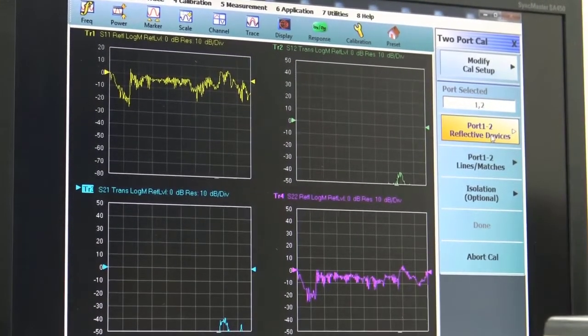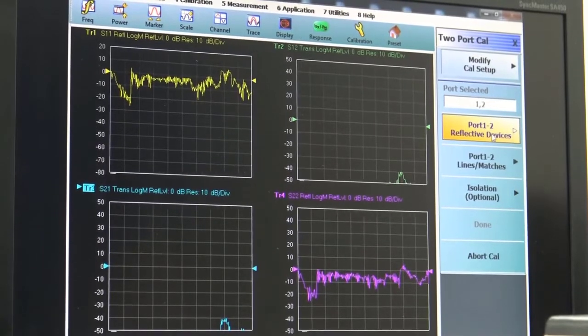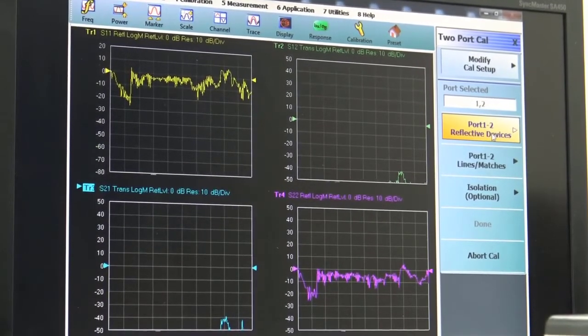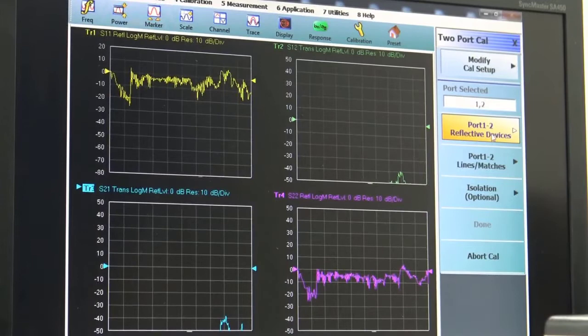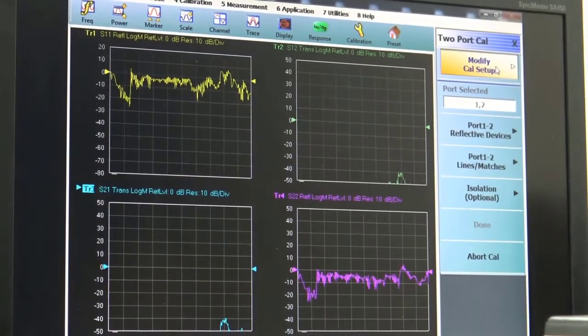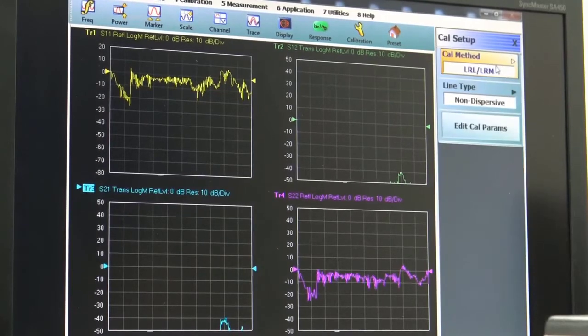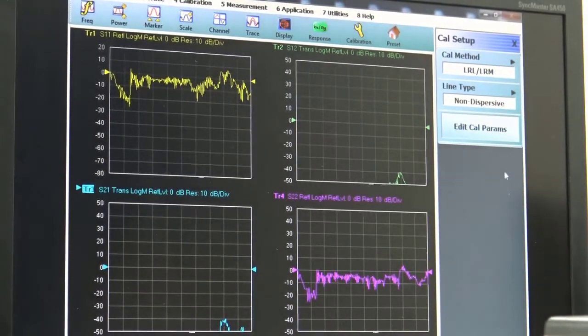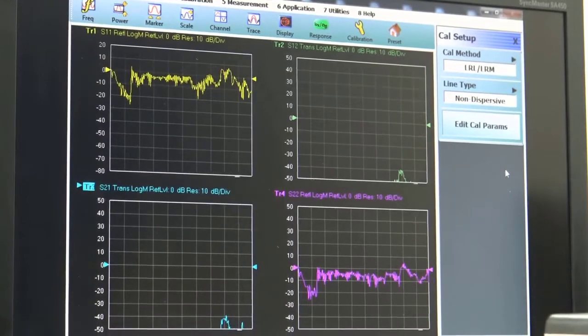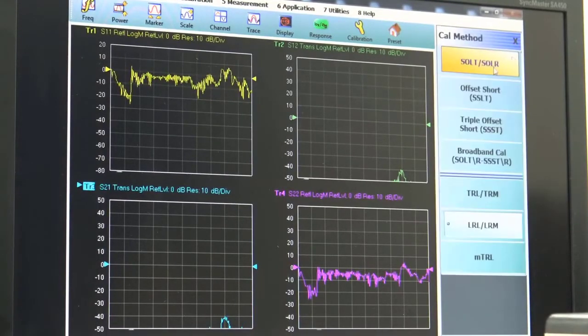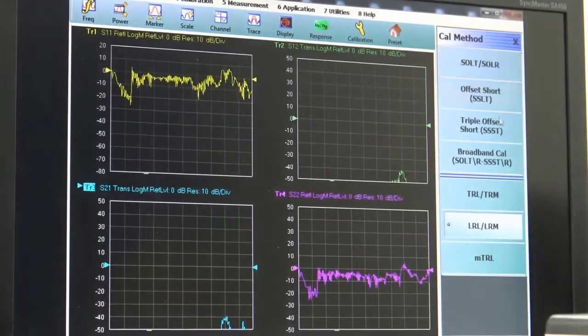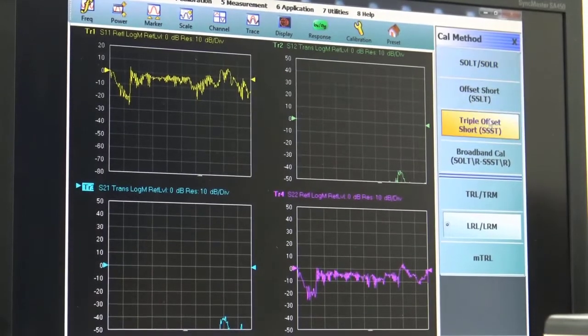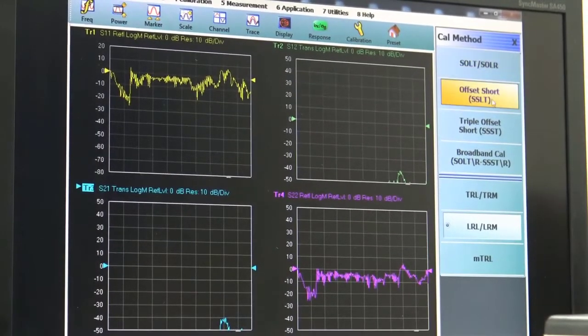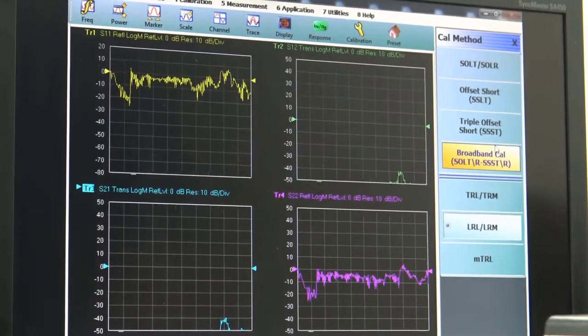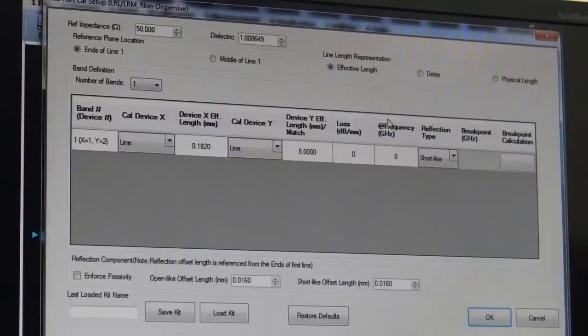But before we do that, we want to make sure that we're set up for the types of calibration that we want in this broadband on wafer measurement. So we'll go first to modify Cal Setup, and this is where we define the type of calibration, the algorithm that we're going to be using. And so if we had a coax setup, then one of these would apply. They would also apply in other situations.